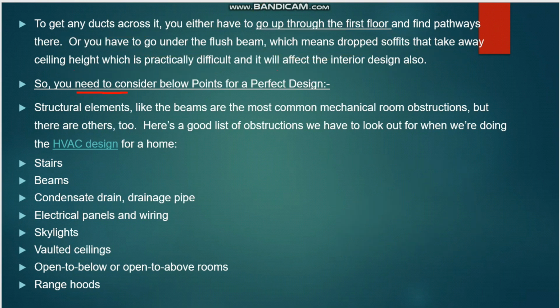So finally, you need to consider the following points for a perfect design at the initial stage for the design engineer. Structural elements like the beam are the most common mechanical room obstruction, but there are others too. Here is a list of obstructions for the design engineer at the initial stage. You have to see the stair, and you have to see the beams. Is there any condensate drain or drainage pipe, a gravity pipe, passing through that area, so that the duct routing cannot be made properly? Also electrical panels and wiring, skylights if there is any, vaulted ceilings, rooms open to below or open to above, and range hoods. These are the different cases we have to consider when we go for the initial mechanical room design.